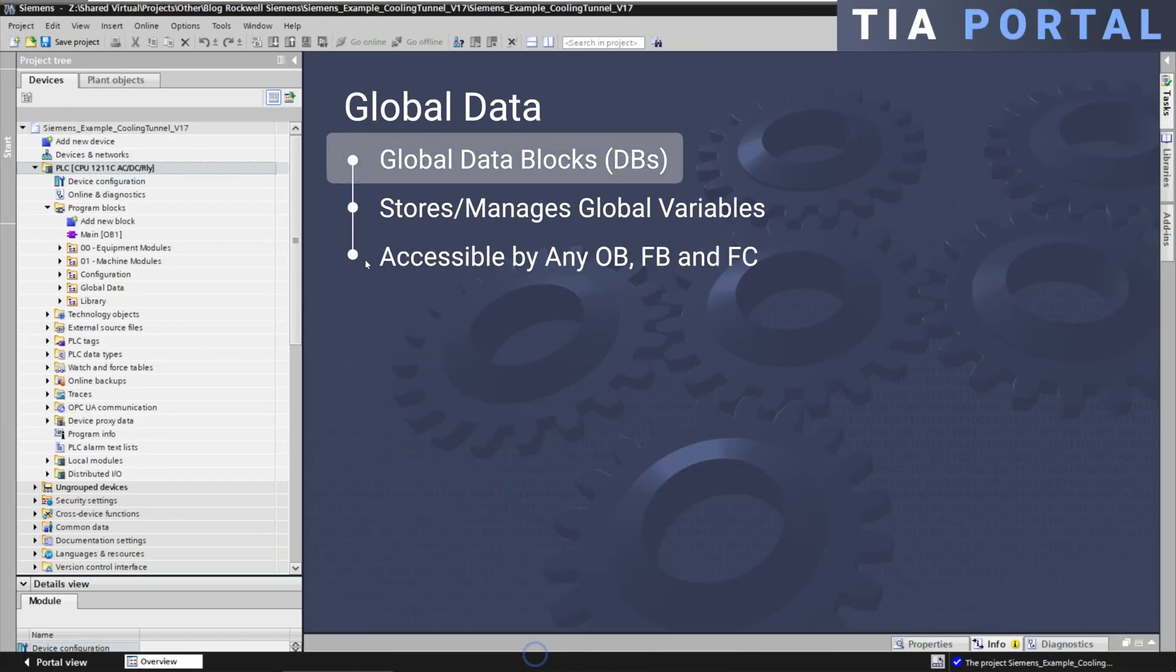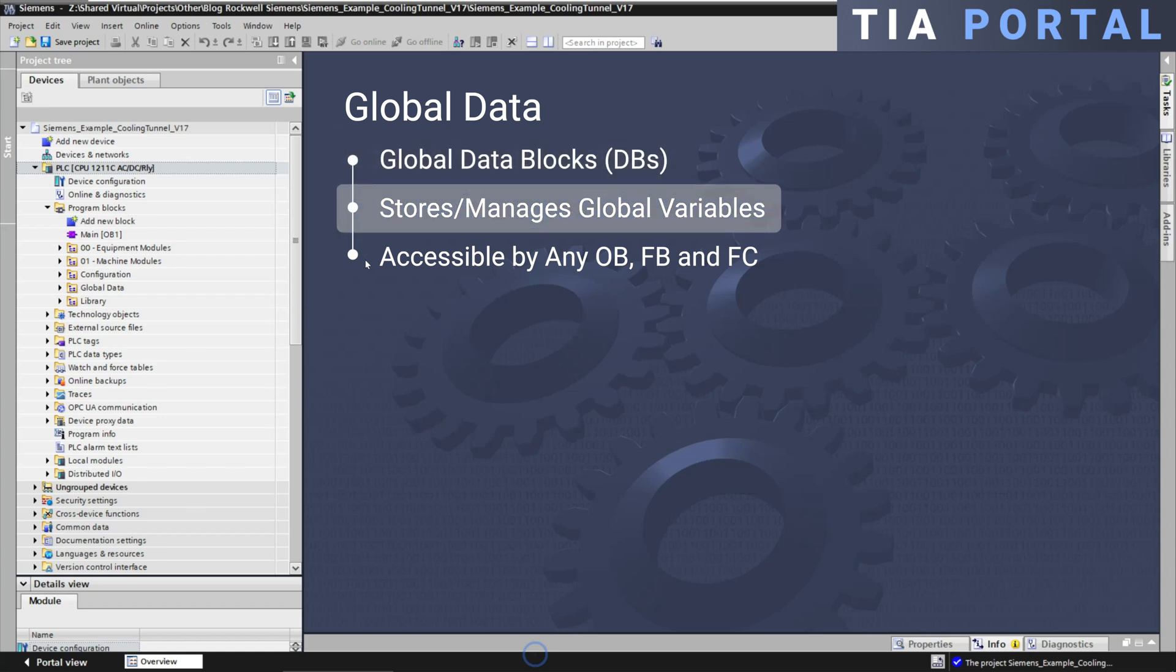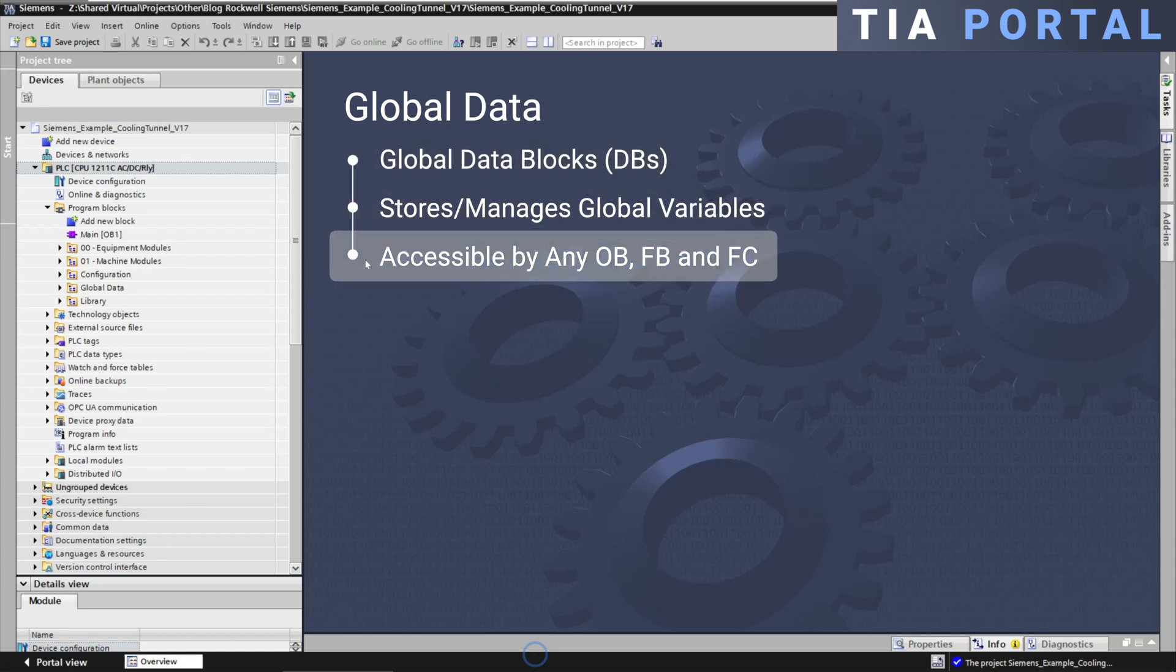Siemens uses global data blocks or DBs to store and manage global variables. DBs can be accessed from anywhere in the PLC project including any organization block (OB), function block (FB), or function (FC).